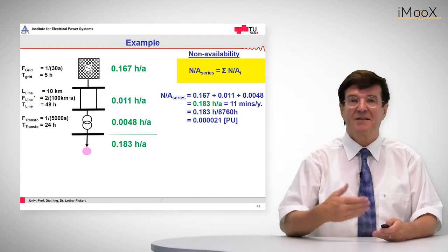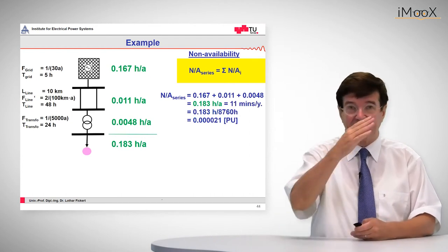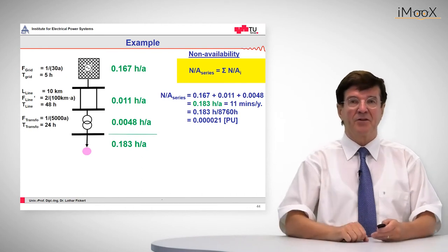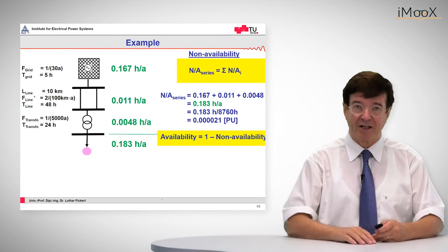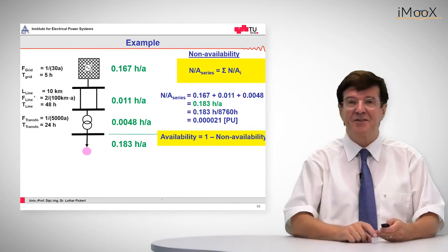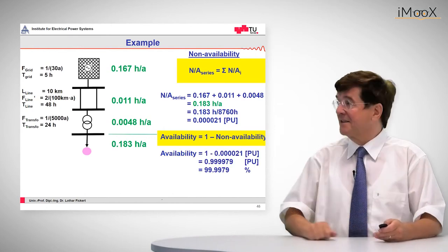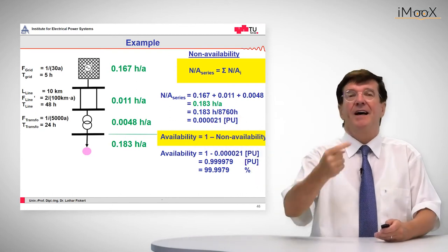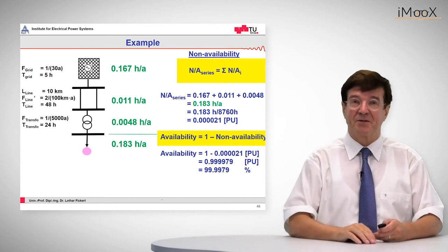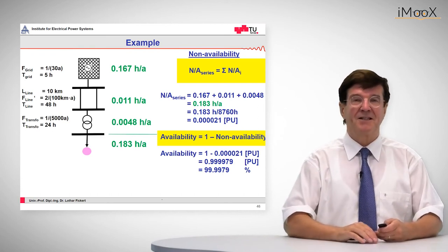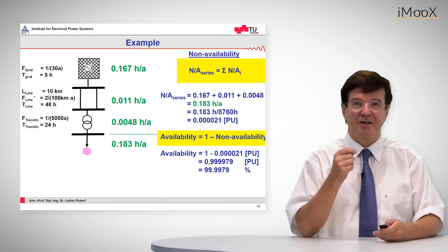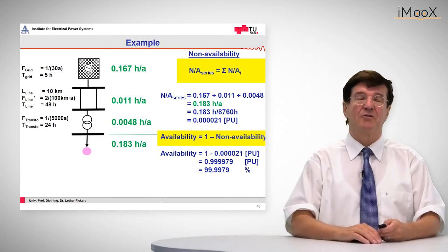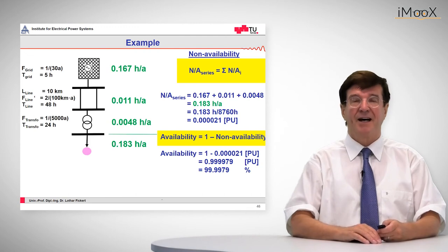In other terms, this is expressed as per unit using 8,760 hours per year. The availability is 1 minus the non-availability, which is 0.999979 per unit. Expressed in percent, the grid is available 99.997% of the observation time of one year. This means it is highly reliable.